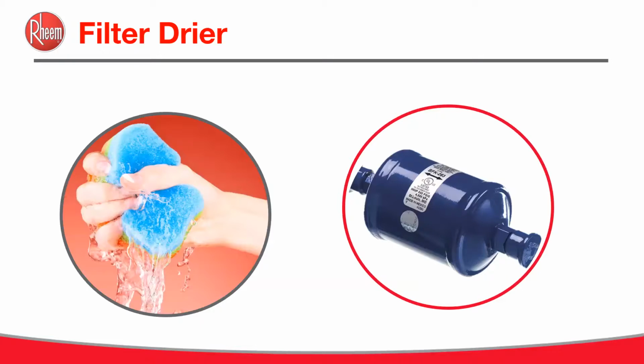Filter dryers. We know filter dryers are used for both heating and cooling, so they're for heat pumps and air conditioners. Also, remember when installing the filter dryer, you always install it in the coolest area. Why? This helps ensure the dryer holds the greatest amount of water. Heat pumps also require a biflow, so it has an arrow on it. The filter dryer must go both ways. You can't use a single direction filter dryer, whereas air conditioners only require a single flow filter dryer.